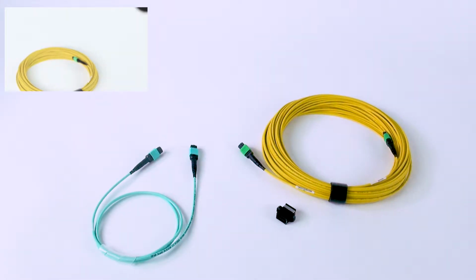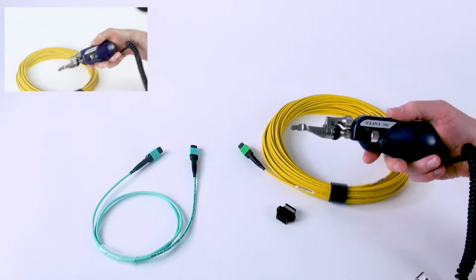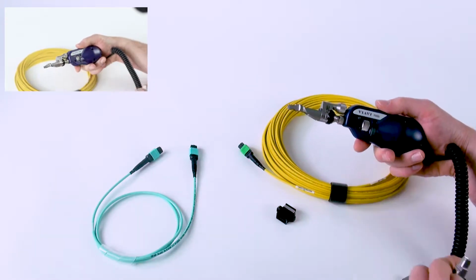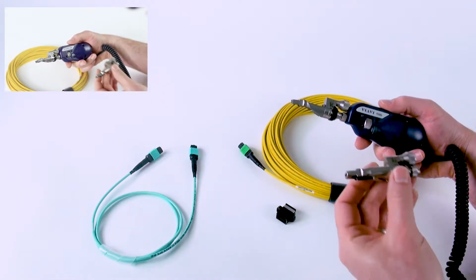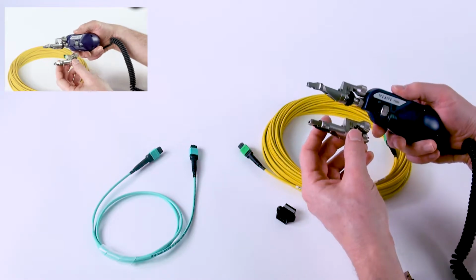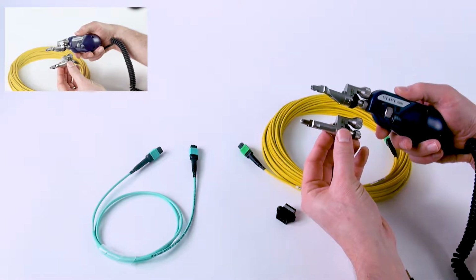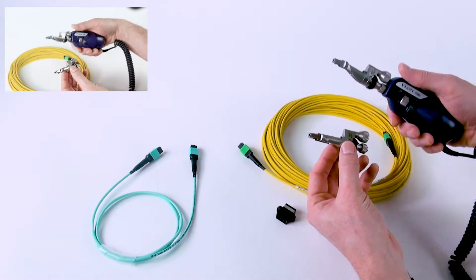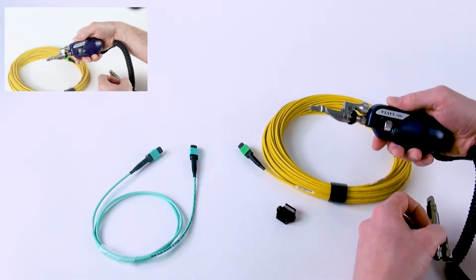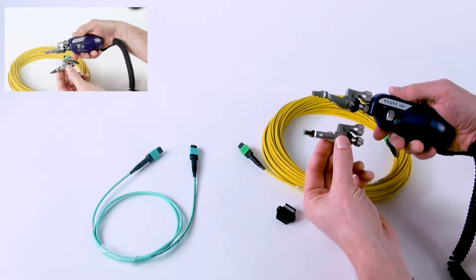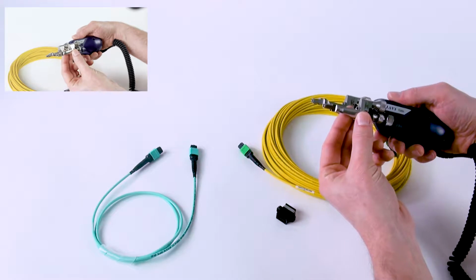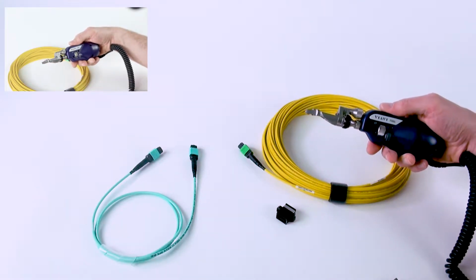Another popular option is to use our P5000i probe with a ribbon tip on the end of it. Here's an example of the APC one along with the flat one—this would be used for inspecting single mode, and this would be used for inspecting multi-mode. It just attaches directly onto the probe itself.